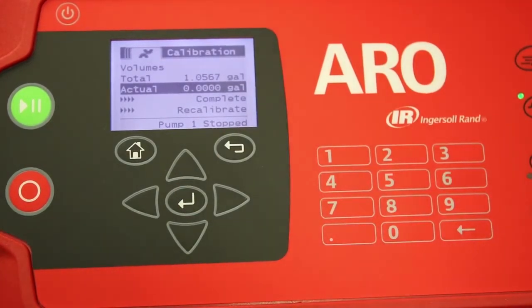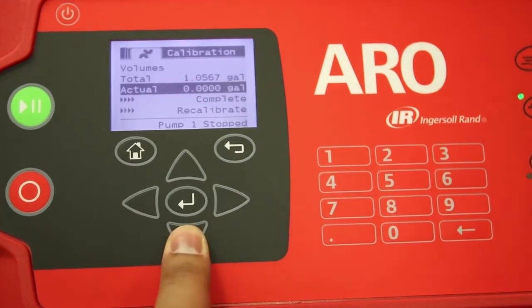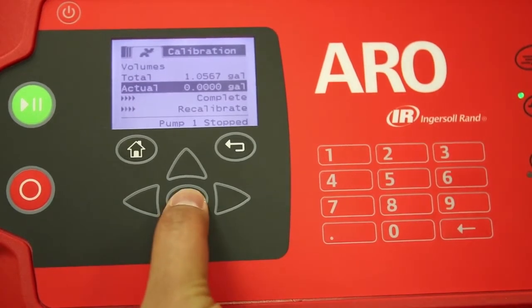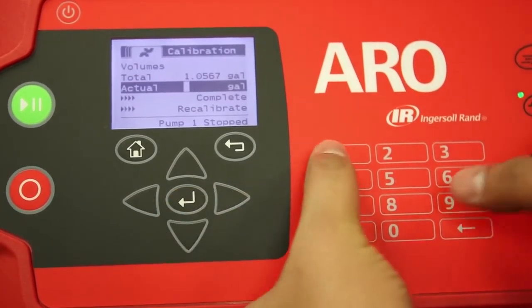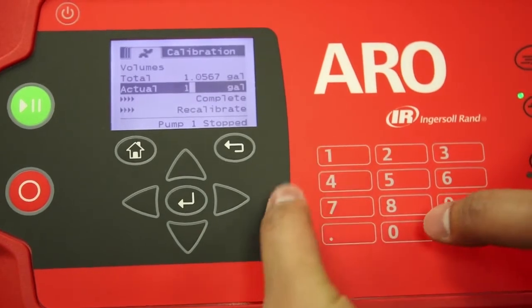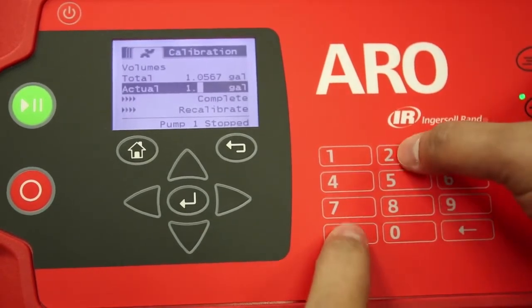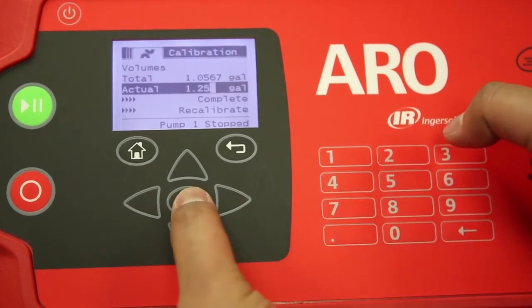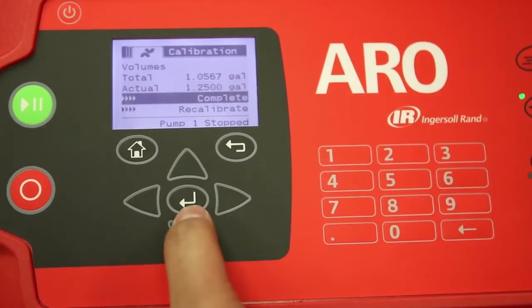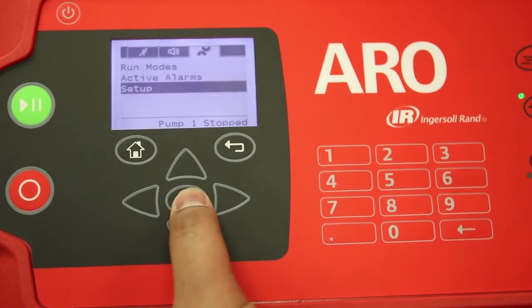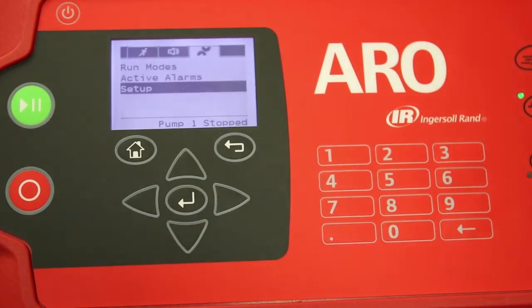We now measure the calibrated cylinder and measure the quantity of fluid present in the cylinder or the bucket. Once the quantity is known, we enter the actual volume. In our case, it is 1.25 gallons, and select complete. The controller has now performed calculations with the actual quantity in the bucket, and the calibration process is complete.